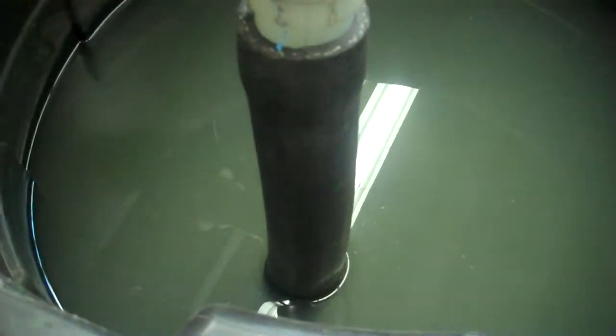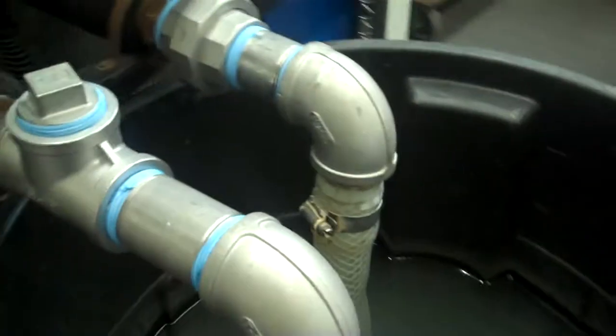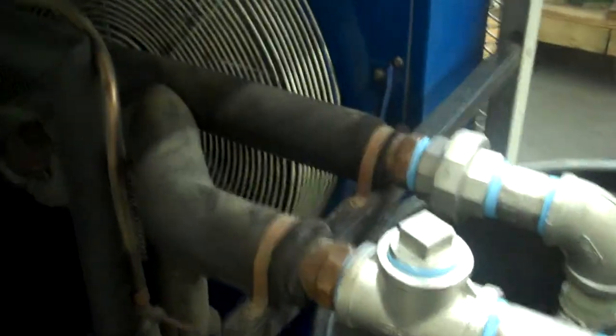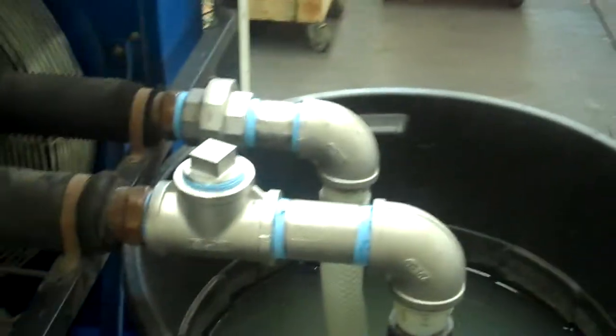The unit does not have a reservoir tank, but the way this is set up, the suction side of the pump comes up and receives fluid from your process. In this case here, our tank. You can set it up either with your own closed loop process if you don't need a reservoir tank, or you could connect it up to your own little central system or tank.